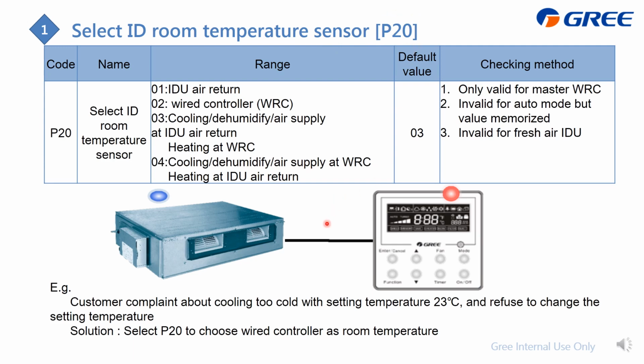Actually we have two sensors for this indoor unit. For example, if we connect to the duct type, one is at the air return here, the other is at the wire controller. And according to the setting, you can improve the room temperature detection accuracy or sensitivity. And we have these 4 options for you, to decide where the room temperature sensor is.